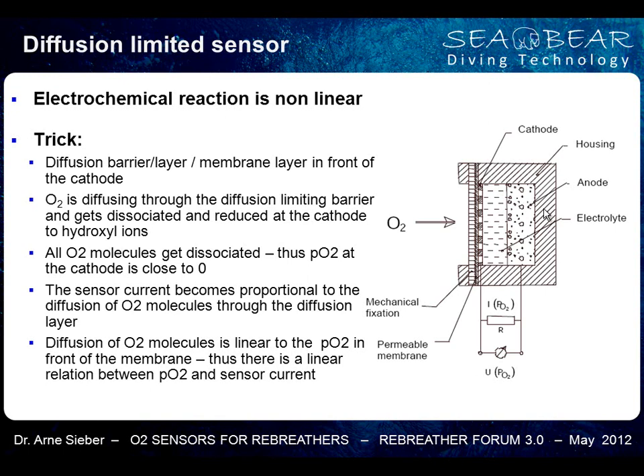So the equation that I showed you before about oxygen sensors shows in principle the functionality of oxygen sensors, so that oxygen is reduced and we have 4 electrons. This is an electrochemical reaction that is absolutely not linear. But we all know that the signal that we get is rather linear. So the question is, how do we get that? An electrochemical engineer applies a trick. If we look at the sensor, this is the sensor housing around, and there we have this anode material that gets oxidized. In front of this, we have the electrolyte, and then we have the cathode. At this cathode, the oxygen goes into the electrolyte and is then oxidized in the anode. So this is non-linear, but the electrochemical engineer now applies a trick.